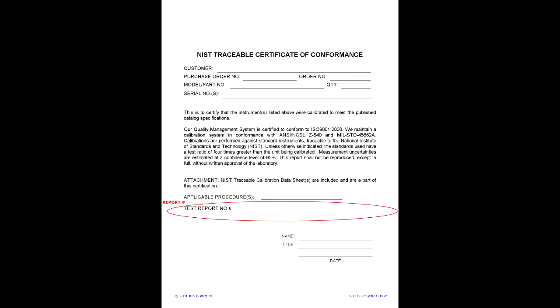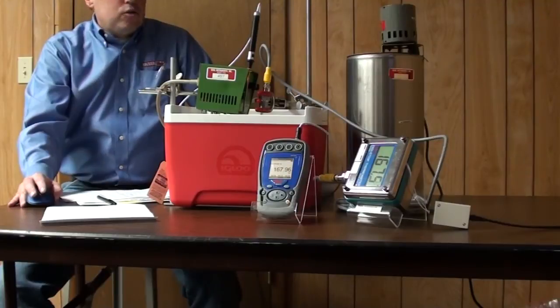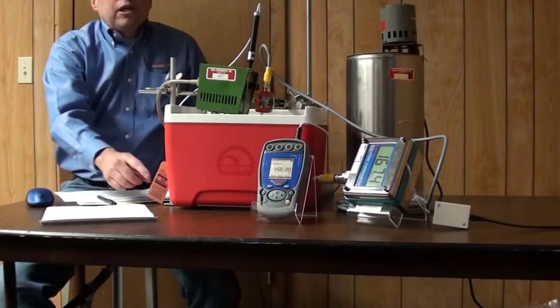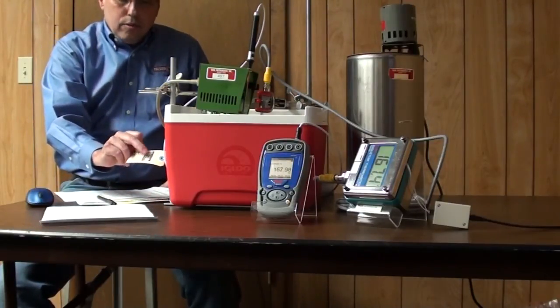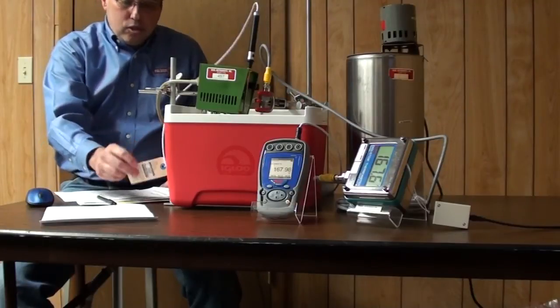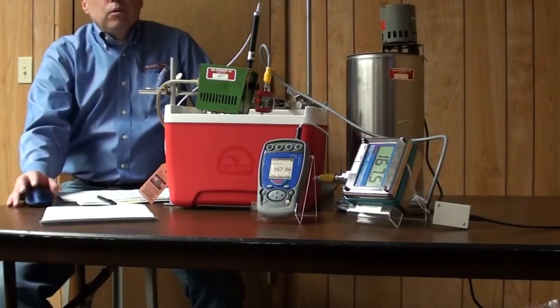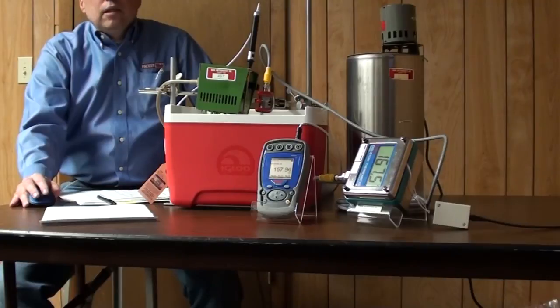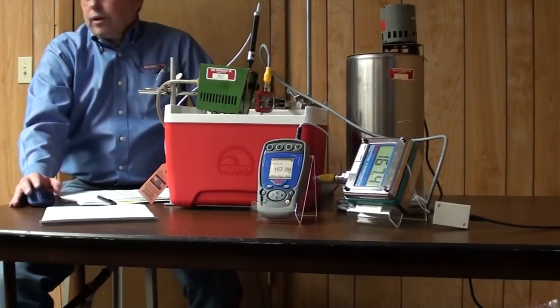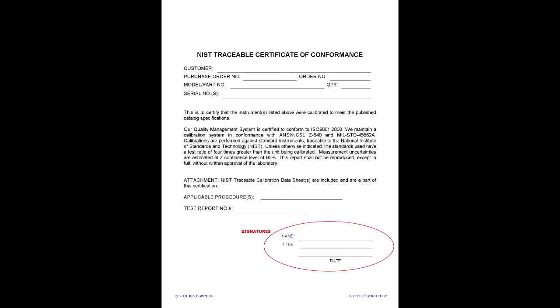Test report number, that's a unique number assigned to the document, and that number also gets printed on our calibration tags here that we put on. It'll say NIST number and then have a number. So if you were to lose a document and you give us that test report number, we can recall everything done about that and reproduce that. And then there's a signature block on it.